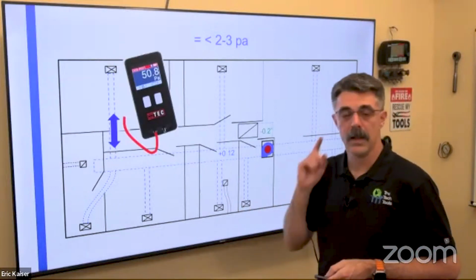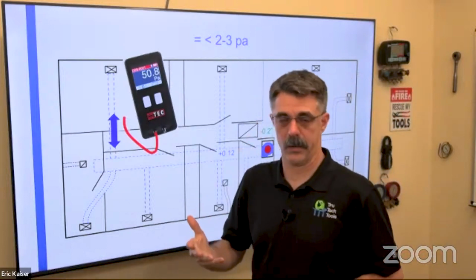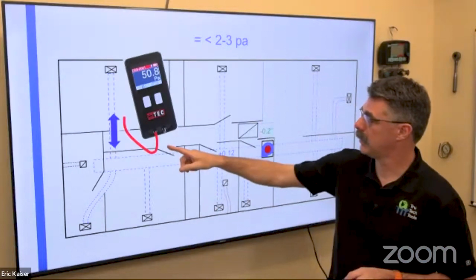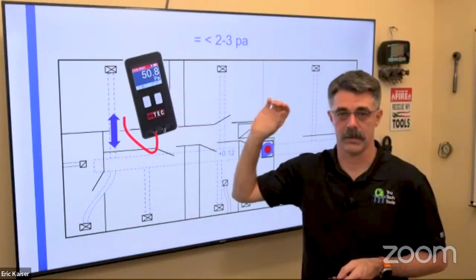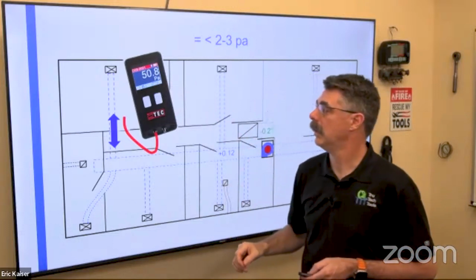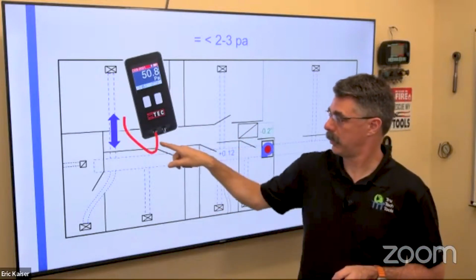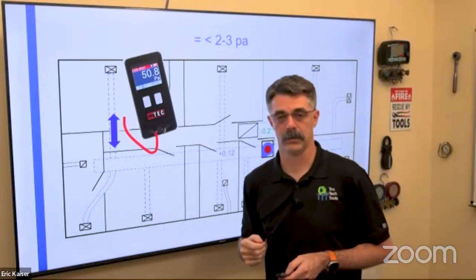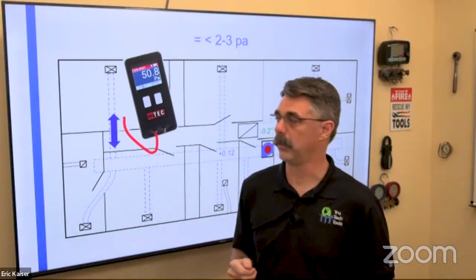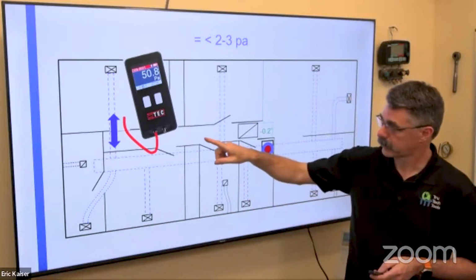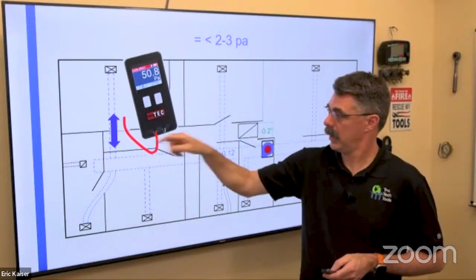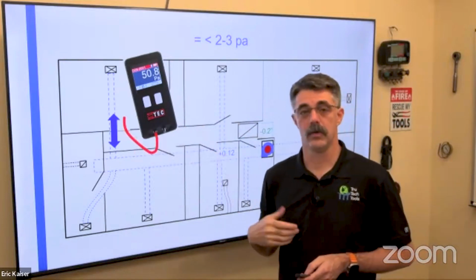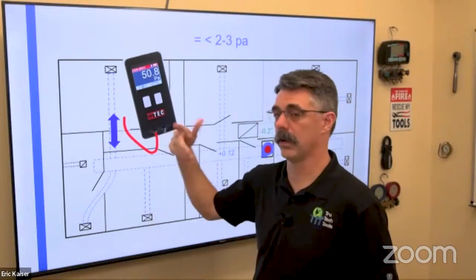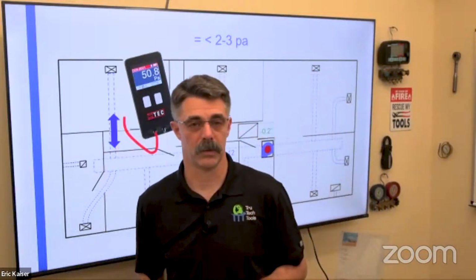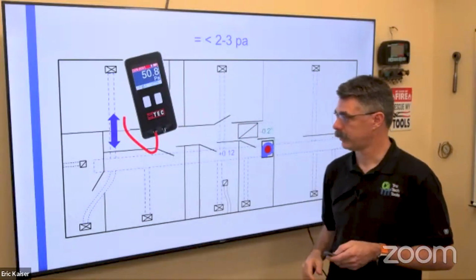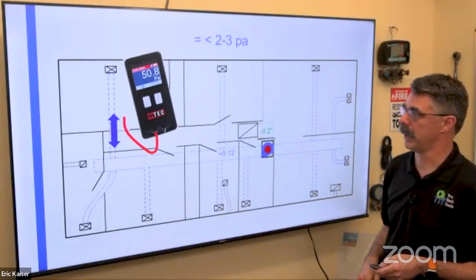All right. Now, this is something that's a really good idea to survey while you're going through. You can take a micromanometer. You need something that reads down in pascals or tenths of a pascal, and read across that door between the room and the house while the door is closed. You're inspecting the house, which we'll talk a little bit more about. That gives you that information, and if you see pressure in there, you may want to increase the transfer, whether put in a transfer grill, a jumper duct, undercut the door more, something along those lines. So that's a great test to take with a micromanometer right there.